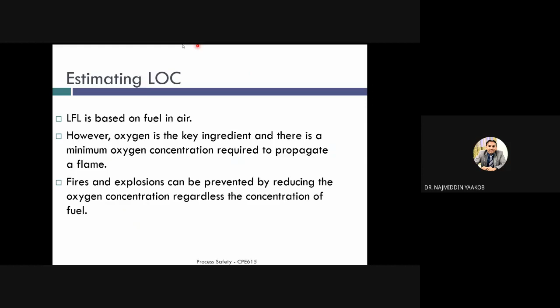LFL is based on fuel in air, how much fuel is in the air. However, oxygen is the key ingredient and there is a minimum oxygen concentration. You need a minimum oxygen concentration required to propagate the flame. That is called LOC. So how do we determine the LOC? The LOC is Z, a constant, times the LFL.